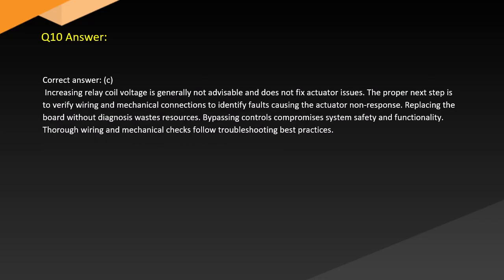Answer. Correct answer: C. Increasing relay coil voltage is generally not advisable and does not fix actuator issues. The proper next step is to verify wiring and mechanical connections to identify faults causing the actuator non-response. Replacing the board without diagnosis wastes resources. Bypassing controls compromises system safety and functionality. Thorough wiring and mechanical checks follow troubleshooting best practices.